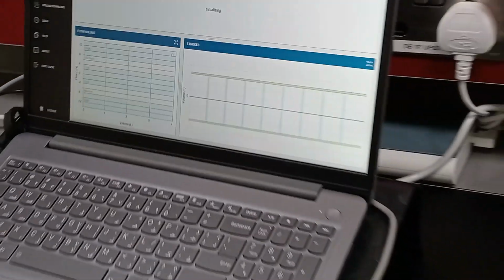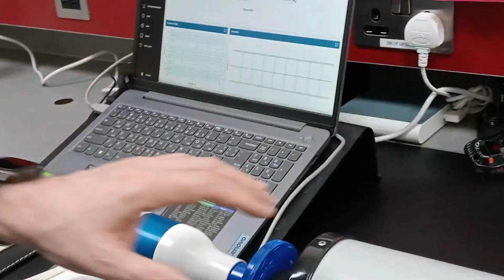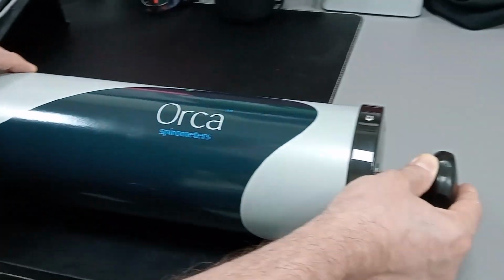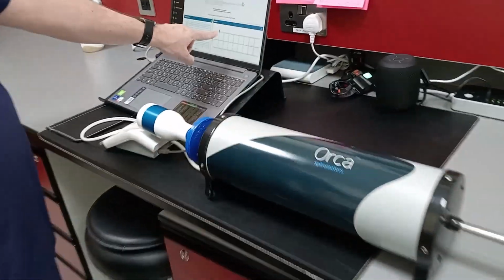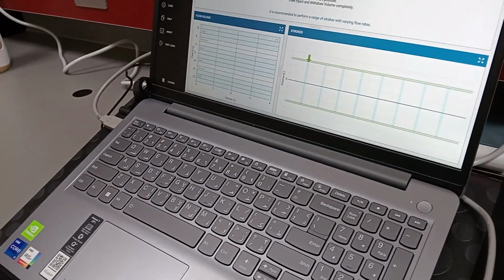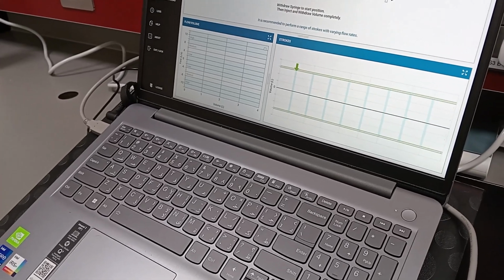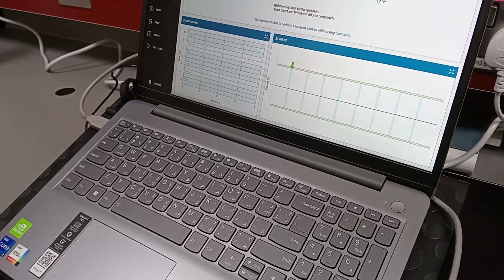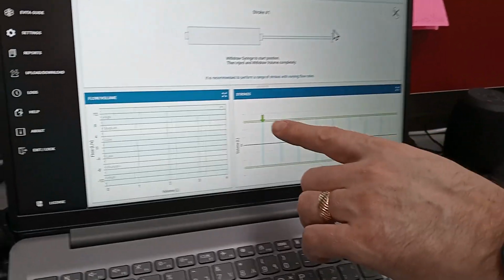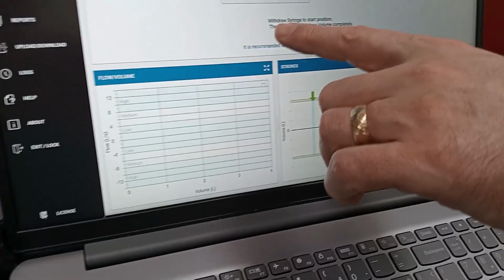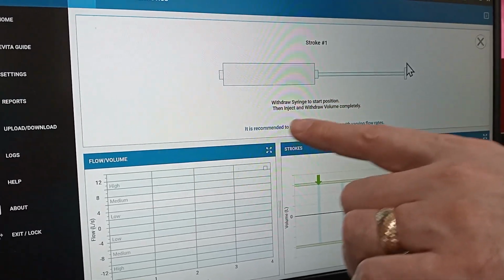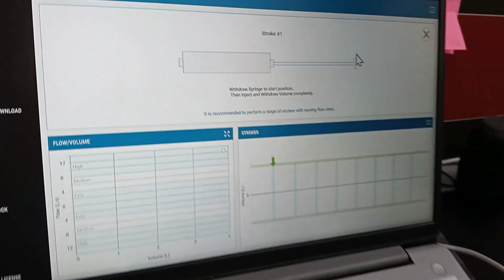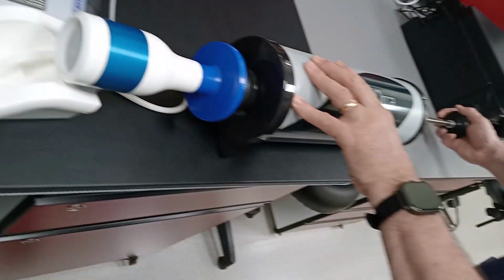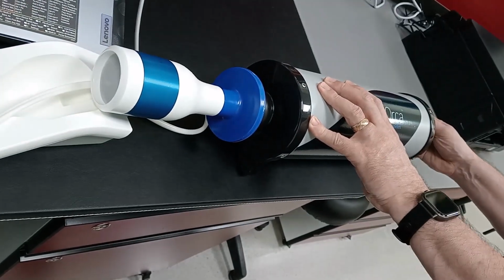So now it will indicate the initialization of the first stroke, and to extend the plunger, which I then maximally withdraw. And then there's an arrow here indicating that I need to discharge the contents of the syringe through the Vitalograph, followed by a stroke back. So the calibration sequence is indicating that it's ready, and the instructions are to withdraw the syringe and then inject and withdraw the volume completely. So I inject the volume and I extract.